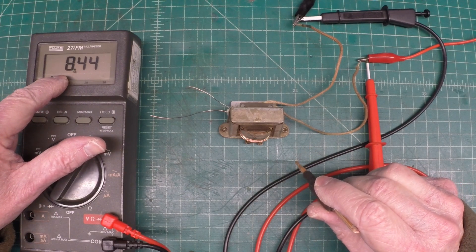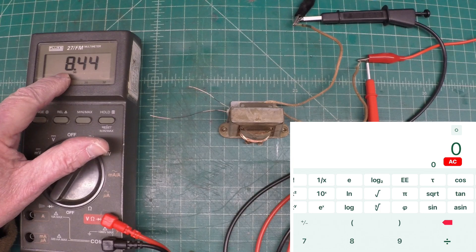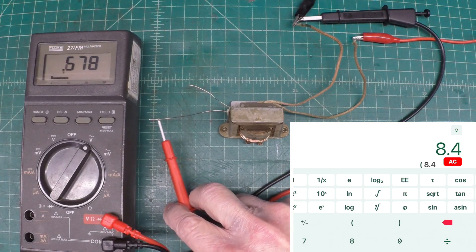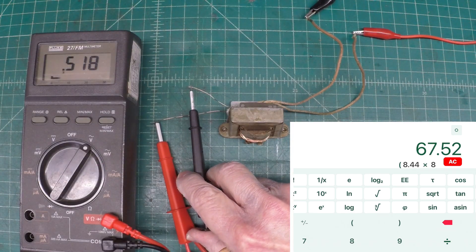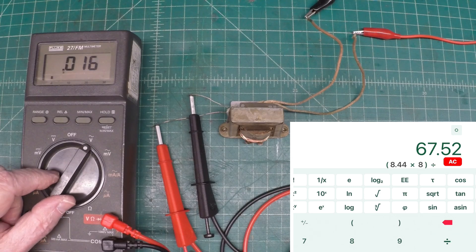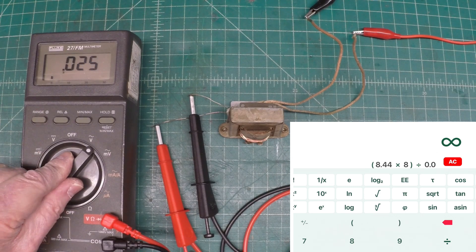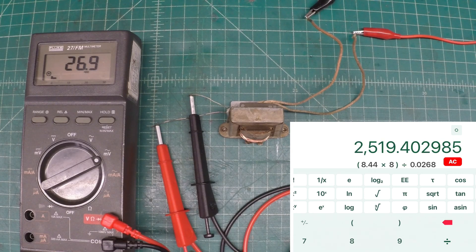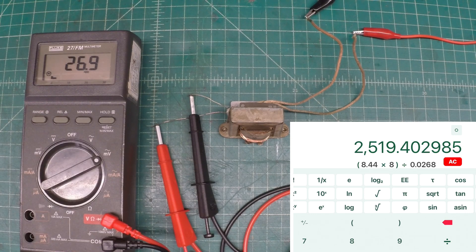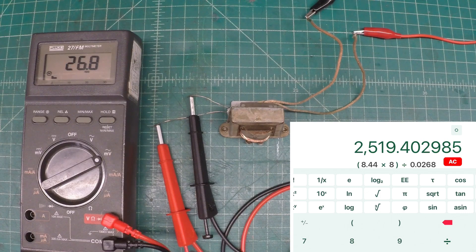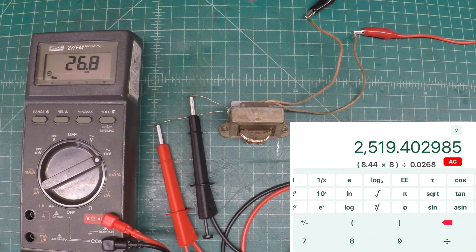I'll pop the math up here in the calculator on the screen and then we'll move over to my eight turn winding. Just for more accuracy I'm gonna flip my meter down to look at millivolts. You can see we're about 26.8 millivolts or 0.0268 volts and that gives me a total number of turns of 2519.